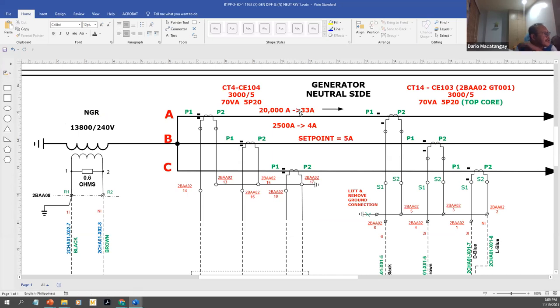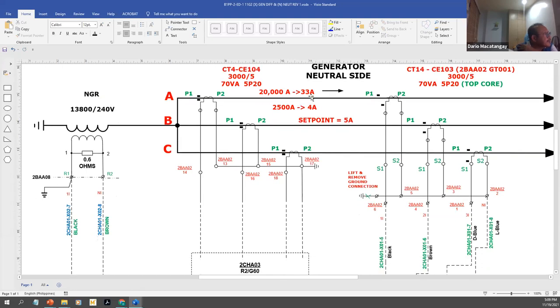So you see 33 amps is a lot higher than the set point, which is 5 amperes. So it's going to trip, okay? This current 33 amps, this 20,000 amps is flowing on the line, whereas this current 33 amps will flow here, over here.